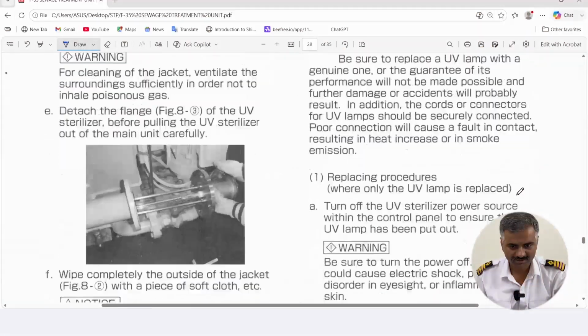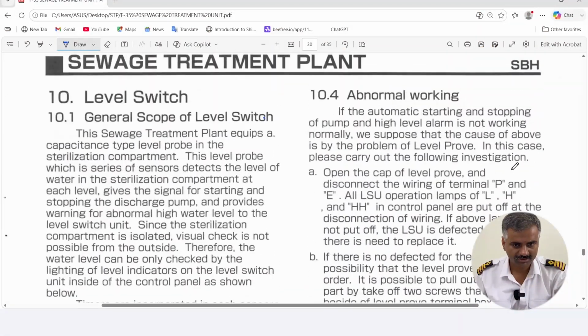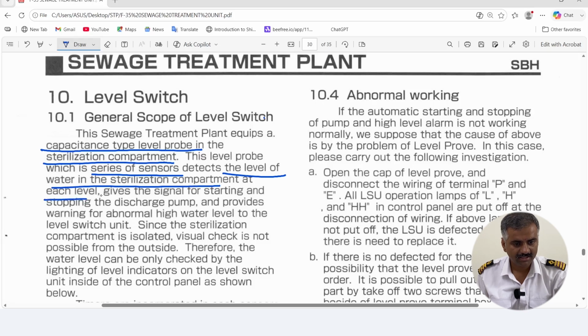So as the manual says, the sewage treatment plant equips a capacitance type level probe in the sterilization compartment, that is the last compartment, where you have a chlorination chamber. The level probe has a series of sensors which detect the level of water in the sterilization compartment at each level. That is a low level, a high level, and a high-high level where you have an alarm. So at high level your pump cuts in. At low level the pump cuts out, and at high-high level the alarm comes.